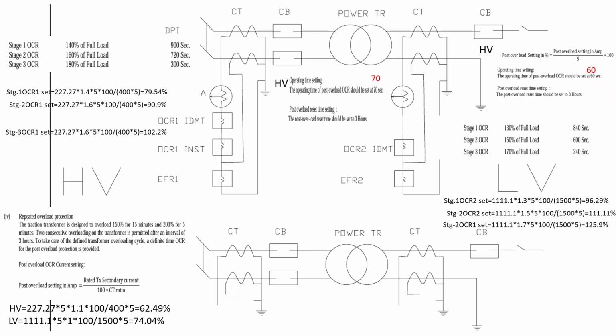And on the primary side we have used two CTs. One is the line CT, another is the earth CT. In the secondary also, though the secondary is earth, our return current comes through the track to the earth leg. The earth is connected with the buried rail and an earthing mesh below the traction substation. So the return current comes to the power transformer that way. So two CTs are used: one is the line CT and another is the earth CT.